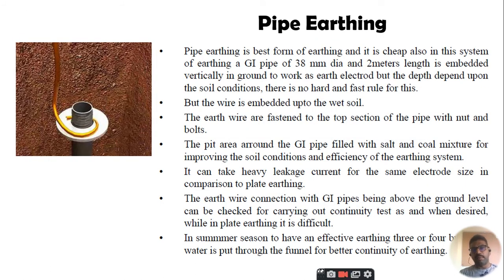The third option is the pipe earthing. Pipe earthing is the best form of earthing, and it is also cheap. A GI pipe of 38 mm diameter and 2 meters length is embedded vertically in the ground, and the wire is embedded up to wet soil. The earth wire is fastened to the top section of the pipe with nuts and bolts. The pit is a new word for us. We have the earthing area where we need to dig a pit, so that is known as the earthing pit. You may also find an earthing pit in substations, in MNC companies, and in a large number of computer centers where earthing pits are required, because they are categorized as non-linear loads. There can be heavy leakage current due to that.